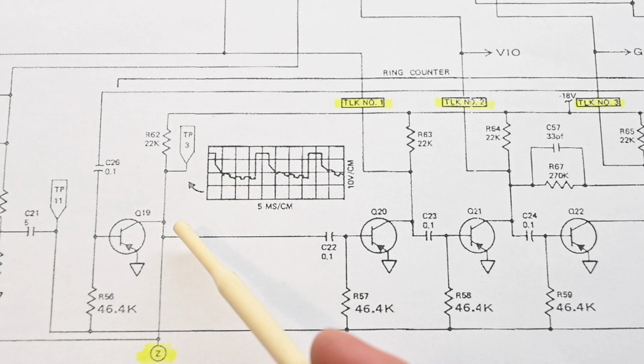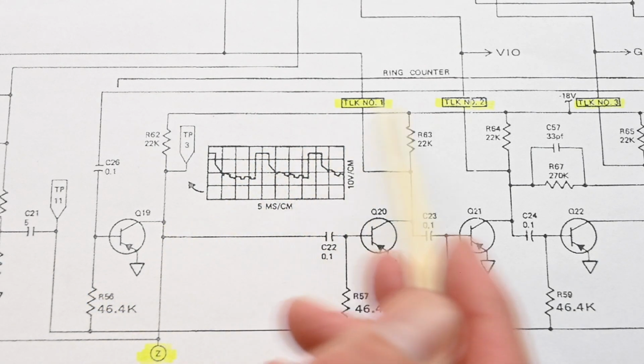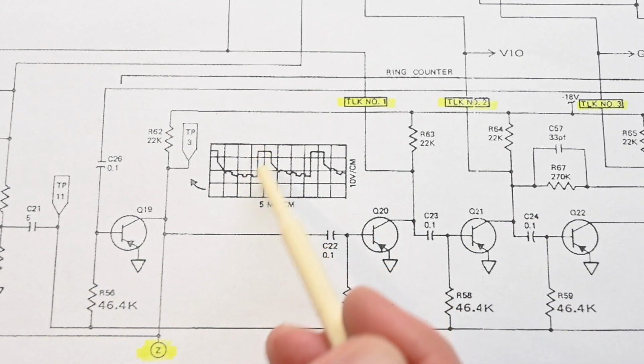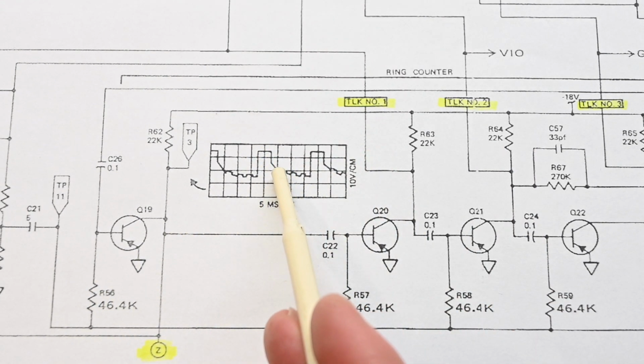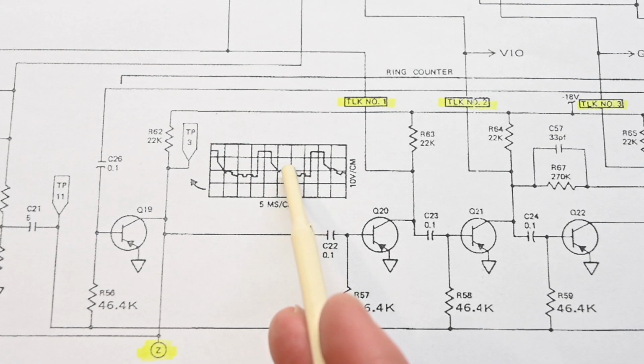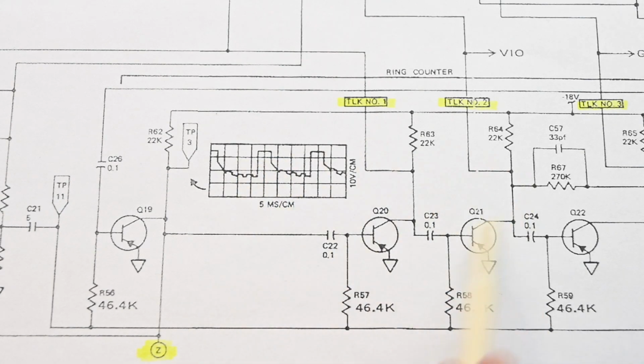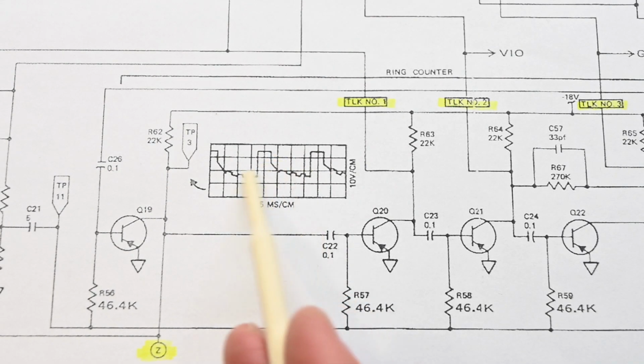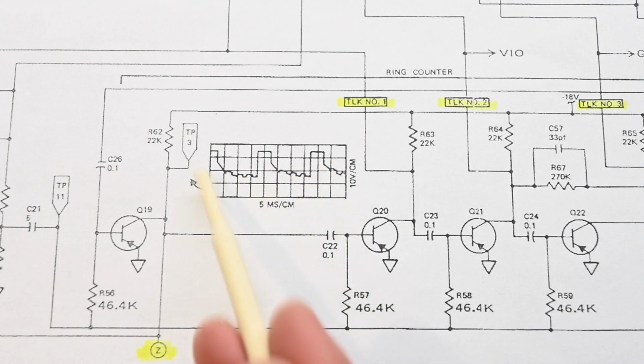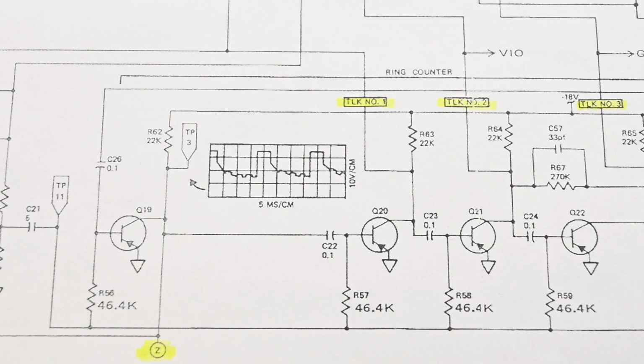But then it completely goes away. But that notch was a clue that I thought maybe this circuit wasn't working correctly because of how poor that waveform looked. And then there's little steps, or right here in this trailing edge, and those look perfectly fine. There shouldn't be any spikes right in this area, and there's a number of small spikes when it's unstable. The service manual mentions that oscillations can create those spikes, and no doubt it's oscillating because it's so unstable until it locks in. All right, so let's take a look at the oscilloscope, and I'll show you exactly how these look, with the actual readings, and we'll continue on with the troubleshooting.